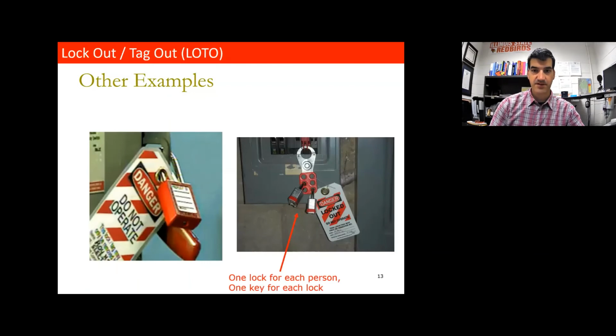There's an example of a circuit breaker over here on the right. Some circuit breakers have holes in them so you can put a lock or a hasp through it. Even the ones that don't have a hole, there are covers for the circuit breakers that you can lock into position, and that's what's being shown here. So this circuit breaker doesn't have a hole, but you can de-energize it and then put a cover over it and lock it so it stays in position. That's what's shown here on the right. This is like a knife switch that you can move up and down, and it's locked in position.